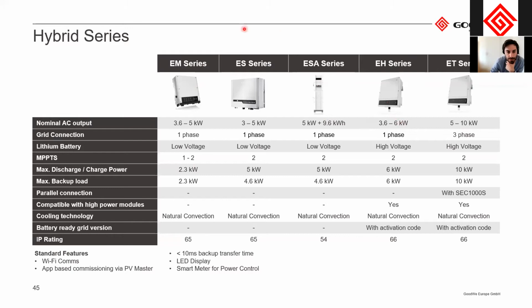Here also you could divide them: the first four are single phase hybrid inverters, and only the last one is a three-phase hybrid inverter, and therefore the T. So firstly, we have the EM and the ES. They both range from about 3 up to 5 kilowatt single phase inverters and are also compatible with low voltage batteries. The EM comes in two models, either with 1 or 2 MPPTs, and the ES always has 2 MPPTs. Also important to mention, for all inverters, they have no fans on the hybrid side. All are cooled with natural convection, since they're all meant also for residential applications.